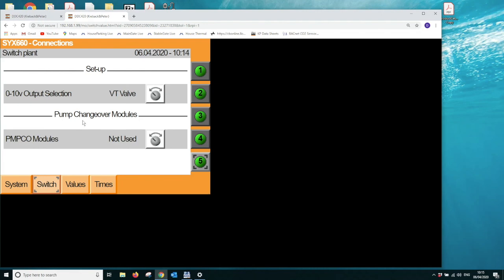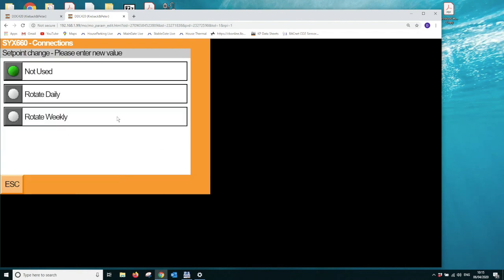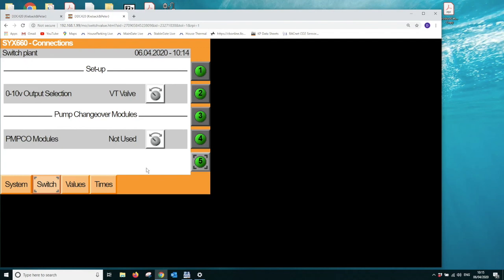So if we are using pump changeover modules, we can effectively turn off those pumps to ensure that they would turn off at one point, either daily or weekly. And that's what that does. You don't need to change the times of those. It just turns the pumps off for something like 15 seconds to allow the pump changeover modules to rotate the pumps. Okay, and that concludes the major setup pages of the SYX controller.